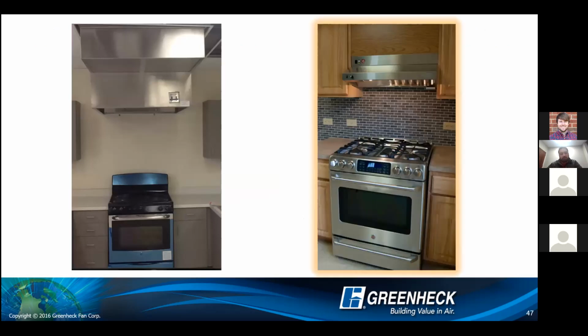Just a little image of these installed versus not installed. The Type 1 hood, here in the old image was our residential range, but it was in a commercial setting, so we had to have Type 1 hood, grease duct, exhaust fans, makeup air fans, supply plenums, all that. Now with this residential range, we have our fully contained fire suppression system. It's very easily hung on a wall-mounted bracket. The contractor installs the bracket, drops this thing onto the 2 brackets. It can tilt forward. You pull the little pin to arm the fire suppression system. Away you go. And then the big thing on the back half of this is you don't need grease duct with these. It's just spiral.